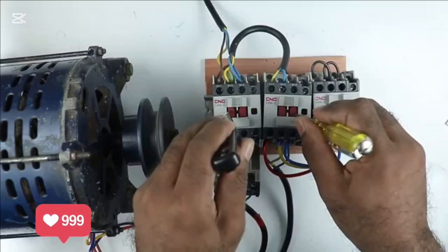So if your star contactor and main contactor is on, then motor will run in star connection. After that, if star contactor goes off and delta contactor turns on, then in this condition, motor will run in delta connection. Friends, if during the connection you somehow performed reverse connection, or if your motor starts running in wrong direction, and you want to learn how to change the running direction of motor in star delta starter, then please click on the right hand side video.